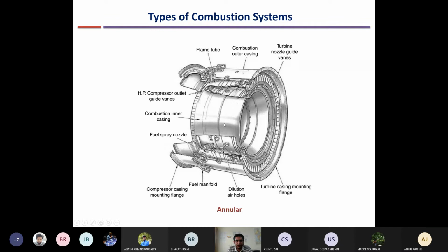However, there are two drawbacks. One is that because these cylinder diameters are large, the stresses generated at high temperature give a tendency to buckle at high temperature. So we should design it with more care, and the design is more complicated. The second thing is that in general also the design is more complicated. Why? Because if you do not design carefully, the flame temperature is not evenly distributed around the periphery. Ultimately after this, the turbine is there.